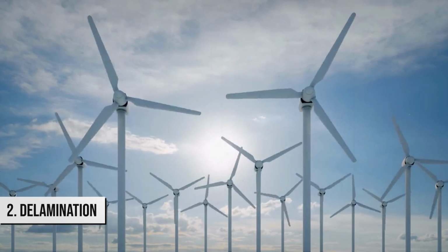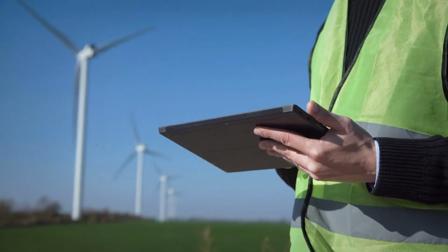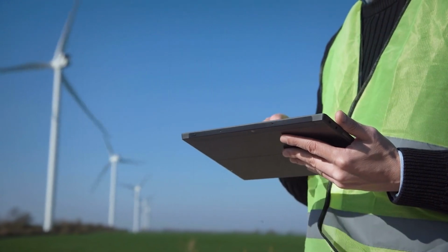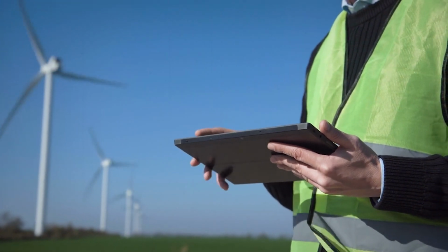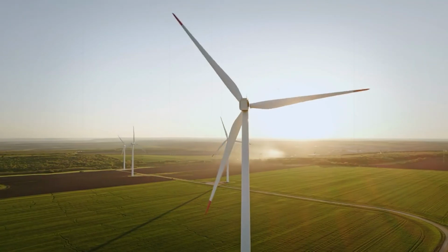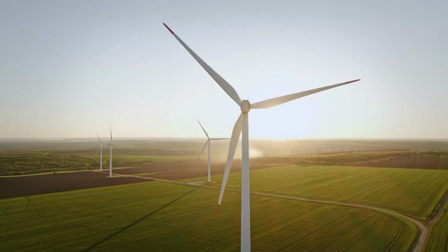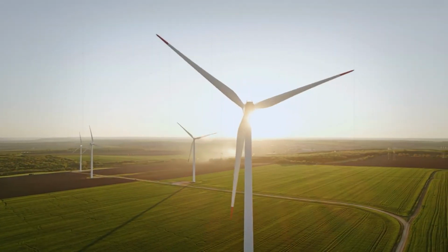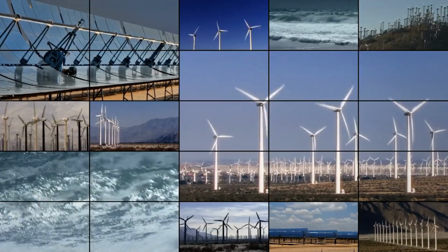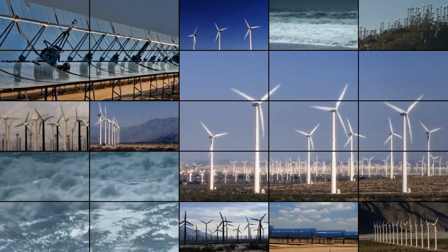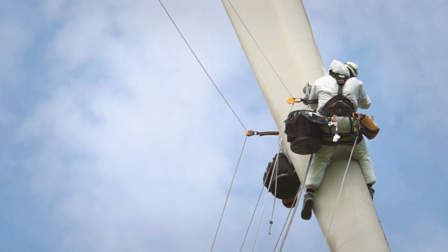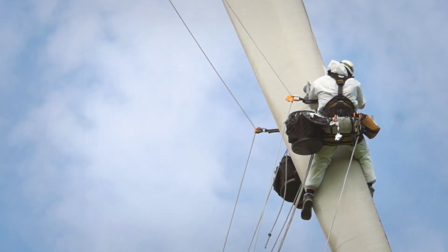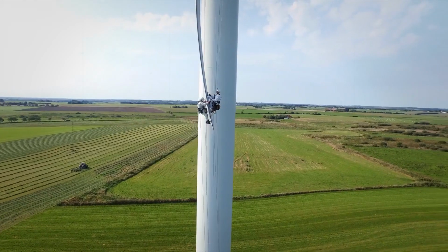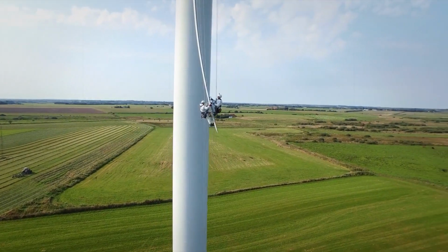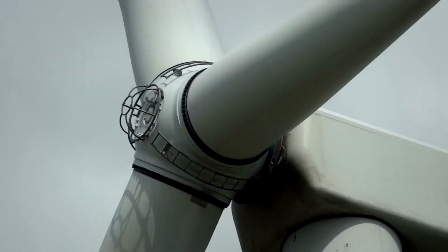2. Delamination. The delamination of the blade is yet another significant problem. Specifically, it takes place when the several composite layers that comprise a blade start to separate from one another. It's like peeling paint or a sticker that starts to lift. Once it starts, it spreads. Low bonding during the production process and high mechanical stress are 2 of the causes. Water gradually infiltrates the material.